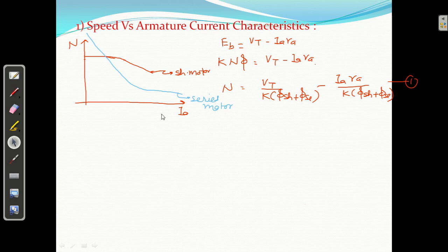So the starting torque required will be very high. With what type of motor do we have to work? A series motor. But whenever you are decreasing the diameter and it goes down to 4 mm or 5 mm, the load on the motor will be reduced to nearly zero. At that time the speed will be dangerously high, so we can't use the series motor. We want a series motor at starting, but at the end we will not use it. We have to limit the speed, so in place of series we will use the compound motor.